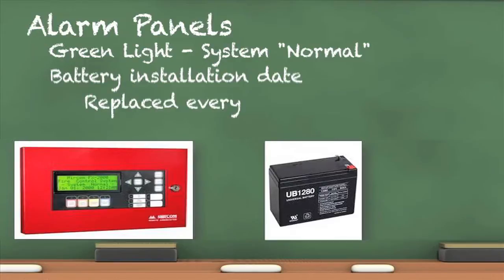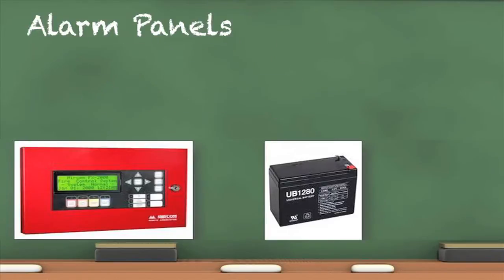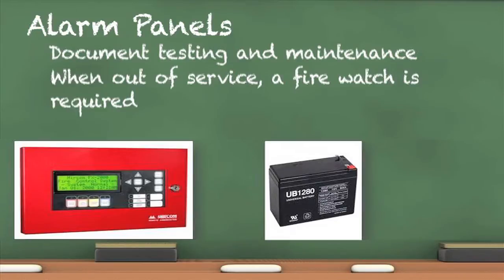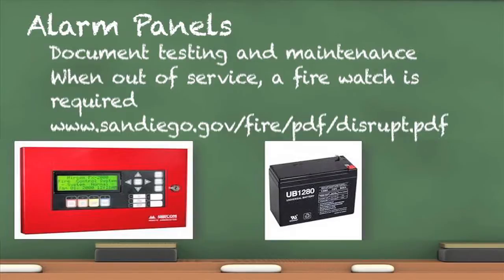Batteries must be replaced every 5 years. Documentation of weekly, quarterly, semi-annual, and annual testing and maintenance of the alarm system is required. If the alarm is out of service, a fire watch is required. The policy and instructions for a fire watch can be found on the San Diego Fire Rescue Department website.